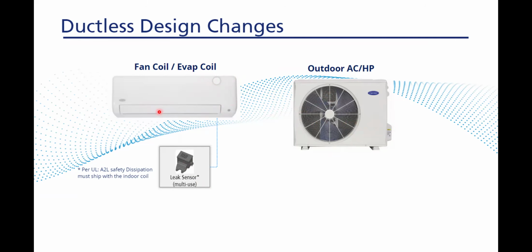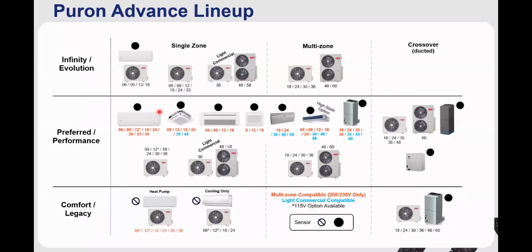There is one weird caveat that can happen with the ductless stuff. Everything's going to be that way I just described for the top tier and mid tier, but for the low end entry level type ductless stuff, those units are not going to be coming with a refrigerant leak sensor. If you are under a certain pounds of refrigerant, the leak sensor is not required at all. You don't have to do it. I forget what it is. Depending on whose article I've read, it's like 3.91 pounds to 4.4 pounds. So something in that range.